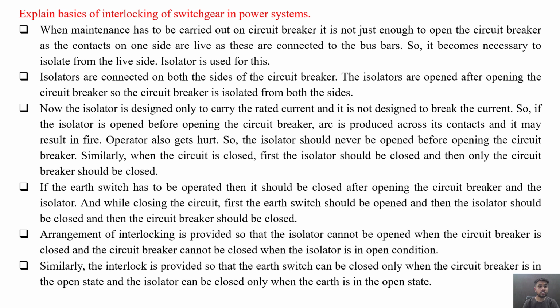Explain basics of interlocking of switchgear in power systems. So when the maintenance has to be carried out on a circuit breaker, it is not just enough to open the circuit breaker, as the contacts on one side are live, as these are connected to the bus bars. So it becomes necessary to isolate from the live side also. For this, isolators are used.